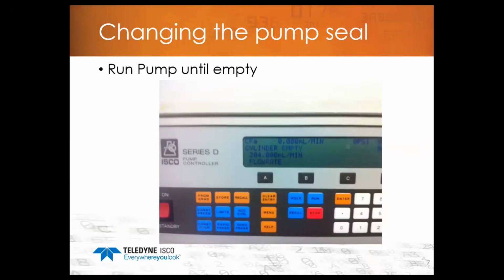The first thing you're going to want to do when you're changing seals is put the pump in a constant flow mode, enter a flow rate, and run the pump empty all the way up to the top. When it interrupts your upper limit sensor, the pump will automatically stop on its own, and you'll get a reading on the display of the controller that will tell you the cylinder's empty. At that point, you'll be ready to go on to the next step, which is removing the cylinder.